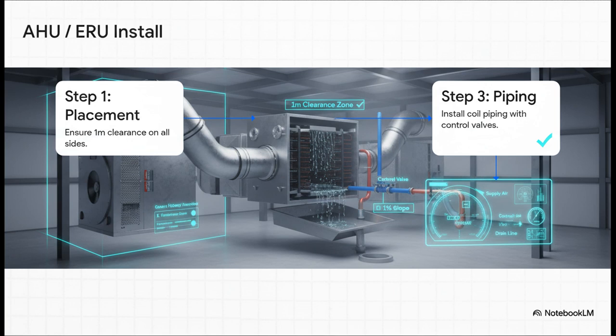Installing a big AHU follows another really strict checklist. Again, step 1 is all about clearance, giving a full meter of space to work on it. Step 2 is connecting the massive air arteries, the supply, return, and fresh air ducts. Step 3, we finally connect our chilled water pipes to the cooling coil inside. But I want you to pay extra close attention to step 4. When air cools down, you get condensation, a lot of it. A drain pan with a strict 1% slope is non-negotiable. It's required by code to get that water away safely, because if you don't, you're asking for leaks, mold, and catastrophic damage. Finally, you test the airflow, the CFM, to prove it's delivering exactly what it's supposed to.